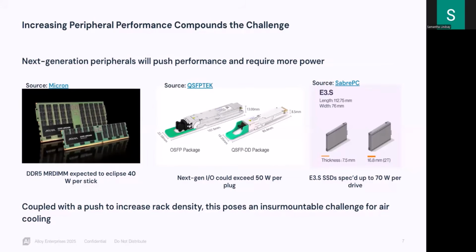And not only that, you want to push those closer together -- increase the density of the rack, get more memory in there. That means higher heat loads packed closer together. All of a sudden, this memory stack-up that wasn't a problem a year ago becomes a critical system heat driver you have to deal with.